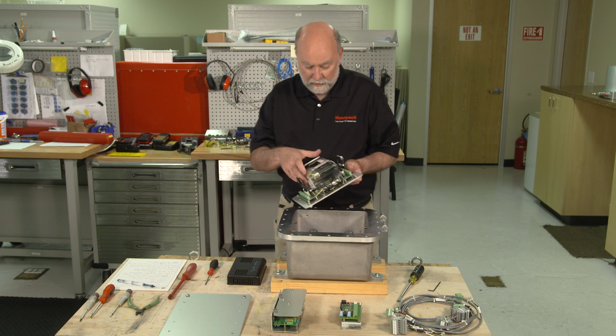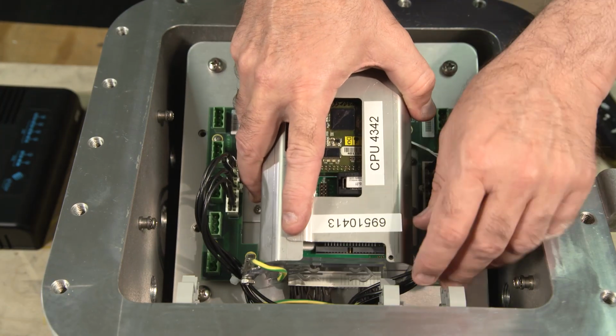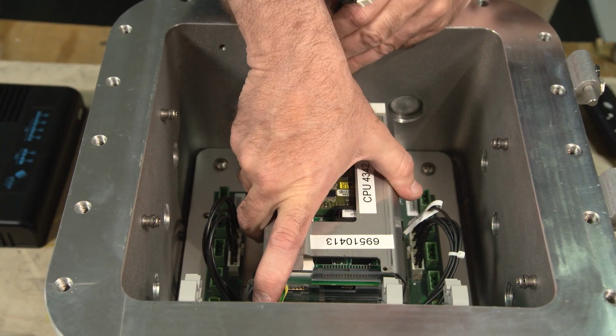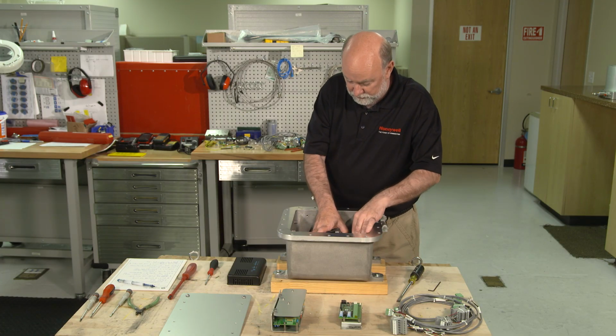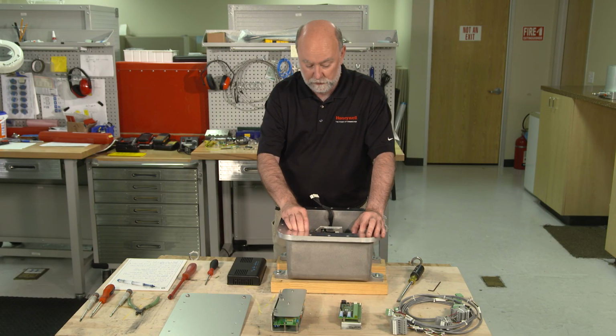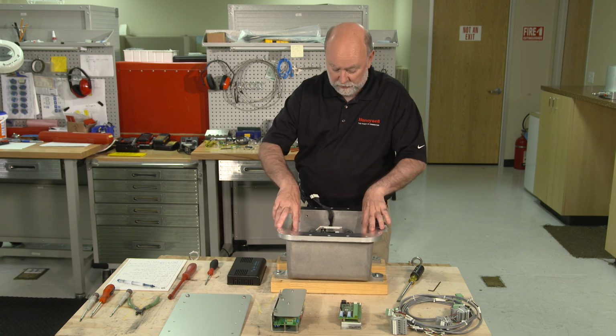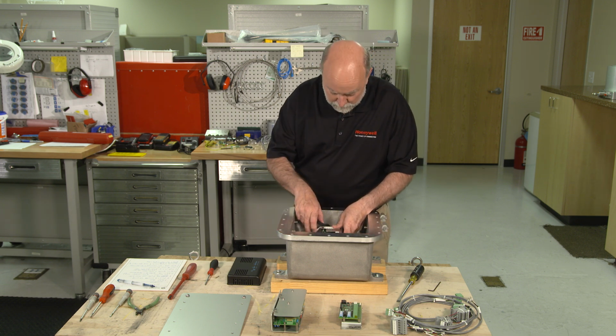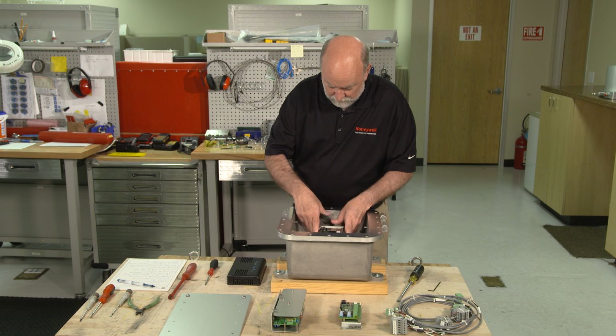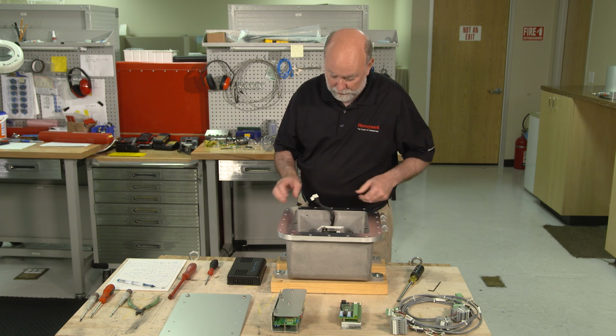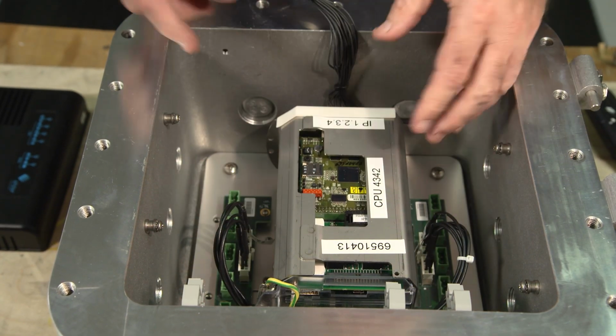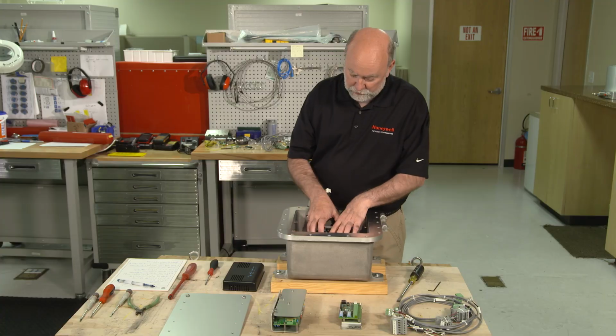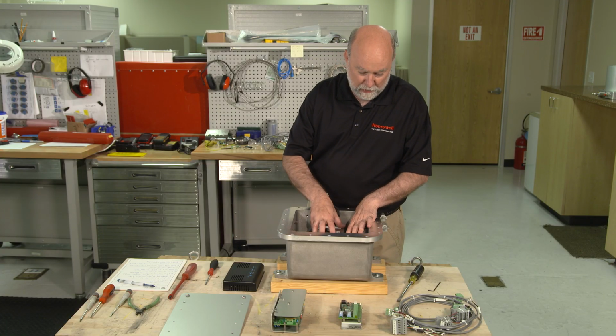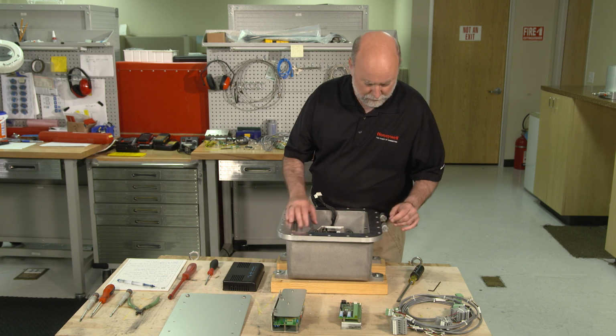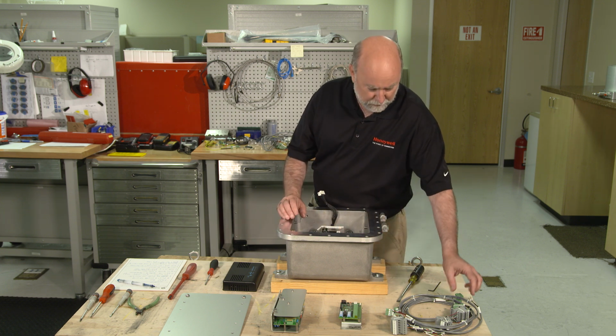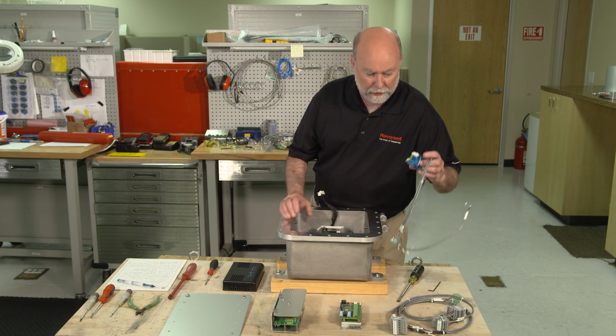I'm going to set the square plate oriented in this direction down into the box at this point, which is virtually empty, having only the DIN rail and the terminal block separators in here, plus the studs which we have installed. I'm going to pull the plate as far towards the back end where I'm standing here as possible to allow some room to install the terminal blocks. At this point, we're not going to tighten those screws back into the bottom of the outlet box just yet. Okay, we want that panel to be loose to help us facilitate the installation of this wiring harness.